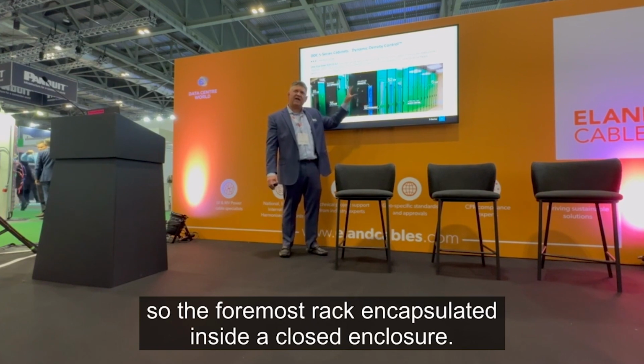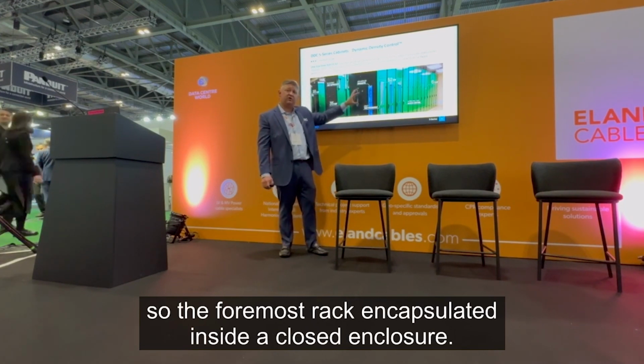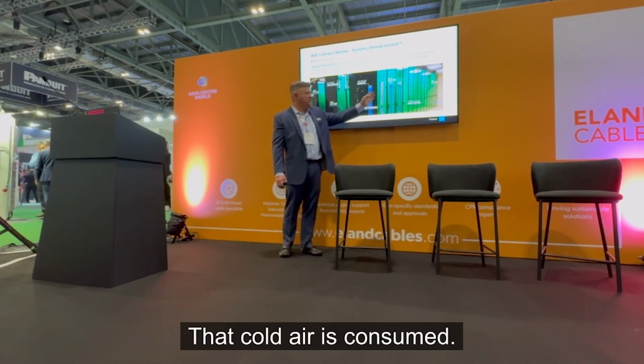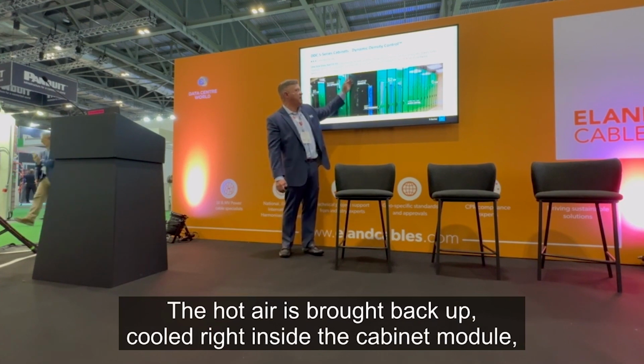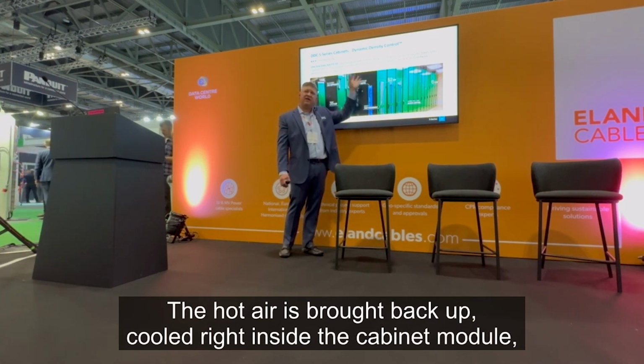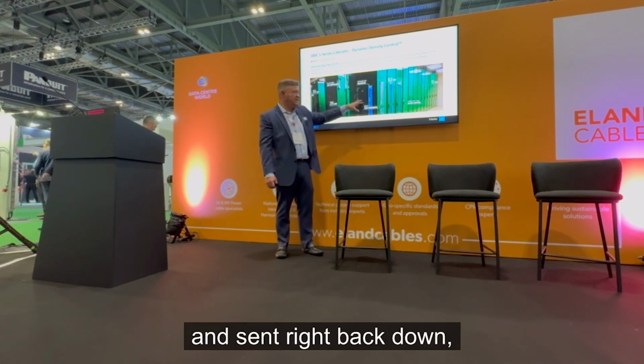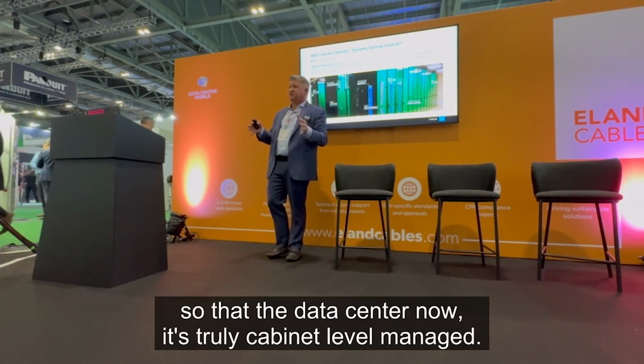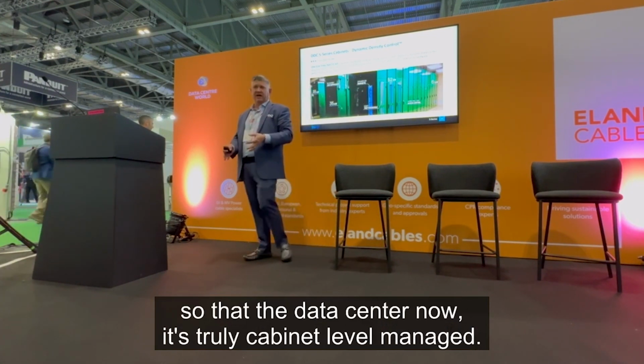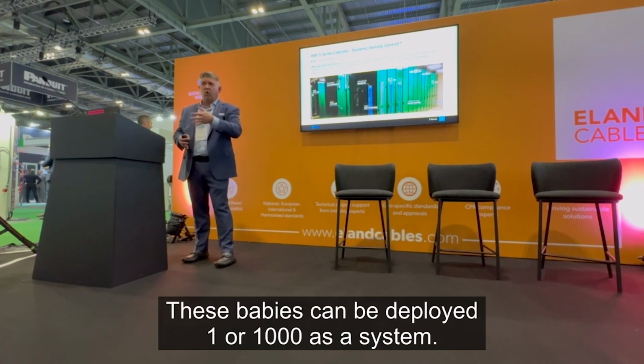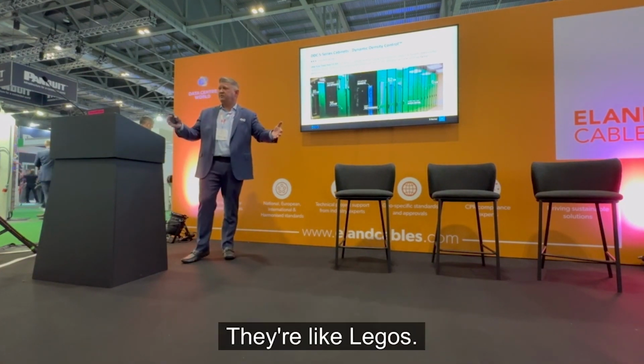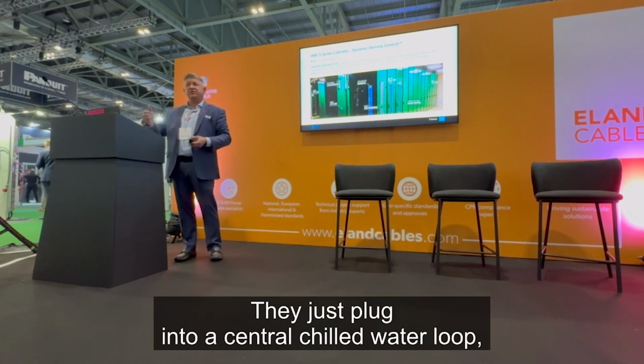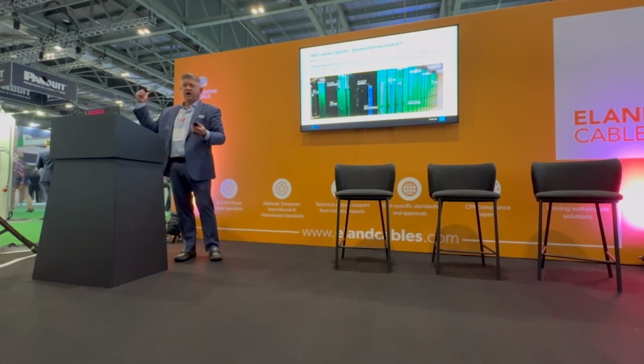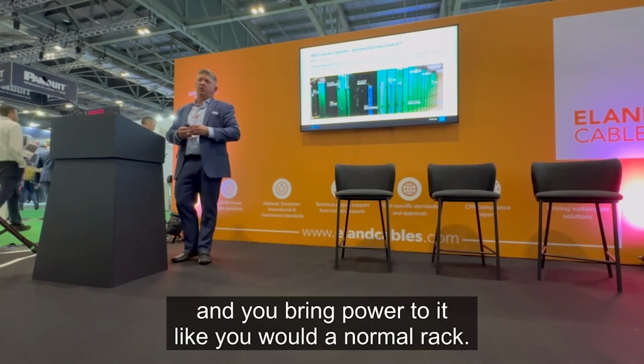The 4-post rack is encapsulated inside a closed enclosure. That cold air is consumed, the hot air is brought back up, cooled right inside the cabinet module, and sucked right back down, so the data center is now truly managed at the cabinet level. These things can be deployed 1 or 1,000 as a system, like Legos. They just plug into a central chilled water loop, and you bring power to it like a normal rack.